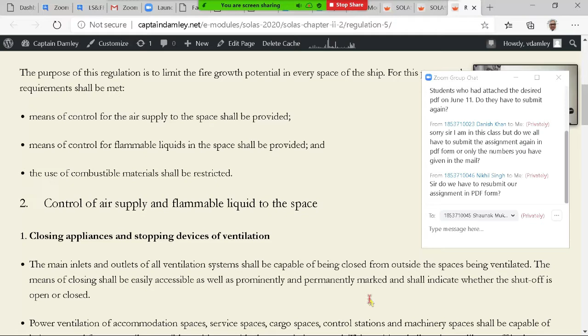One thing always there, that every compartment ventilation system can be shut from outside the compartment, not from inside. It is controlled from outside, so that in case there is a fire in the compartment, you don't have to enter the compartment. You stay out and you stop the air supply. Now, I'm going to go fast on this.